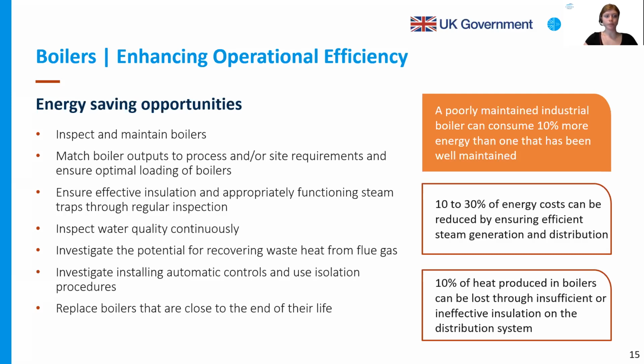Another thing is to investigate the potential for recovering waste heat. That's a very critical thing to have. Investigate installing automatic controls and use isolation procedures for boilers. Replace boilers that are close to the end of life. That goes without saying. Sometimes you tend to operate with boilers that are beyond their life, and that's when they start to give mechanical issues, maintenance-related issues, and then it can be more expensive to maintain them beyond their life.